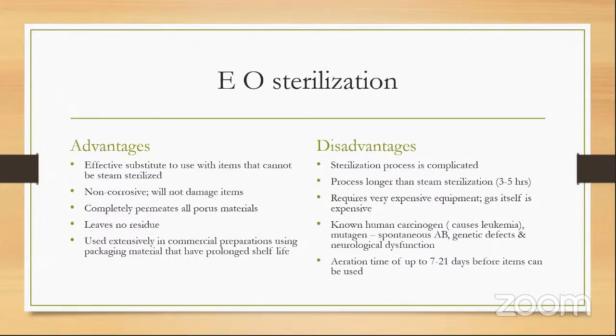The advantage, though, of ethylene oxide sterilization is that it is a very effective substitute to use for sterilizing items that cannot be used for steam sterilization. It is non-corrosive. It will not damage material. It completely permeates all porous materials. It leaves no residue. And ethylene oxide sterilization is used extensively in commercial preparations for articles that have a prolonged shelf life. The disadvantage is that the process itself is quite complicated. It's longer than for steam sterilization.